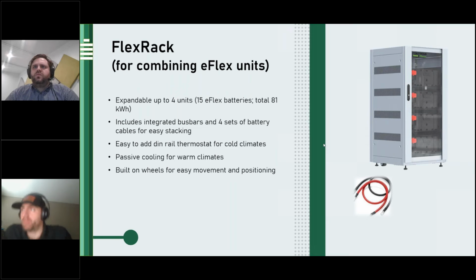One question asks whether the Limitless 15K requires an additional ATS. It does not. One of the beneficial things about the 15K is the built-in 200 amp bypass, so it doesn't need any external equipment. We keep the same standard of three AC outputs: load side, grid side, and generator side. By landing all loads on the load side of the inverter, that allows for the 200 amp pass-through. When the grid fails, we disconnect per UL 1741 compliance and start providing power to the entire panel within 5 milliseconds. So there's no need for an ATS, which helps tie into the whole inverter lineup without adding equipment, especially when finding parts can be difficult. We try to keep it as simple as possible.